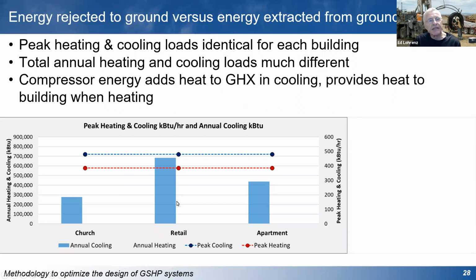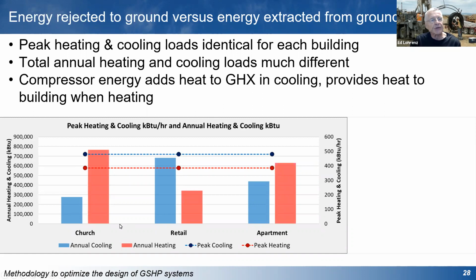Even though the peak load is the same, it's going to be running a lot more hours in cooling than a church would be. Apartment building, probably somewhere in between. Same thing with the heating loads. Church, because you don't have the internal gains from people and lights and things like that much of the week, the heating loads are going to be higher than they would be in a retail store or in an apartment building. But that really doesn't show you how much energy we're actually transferring to and from the ground.